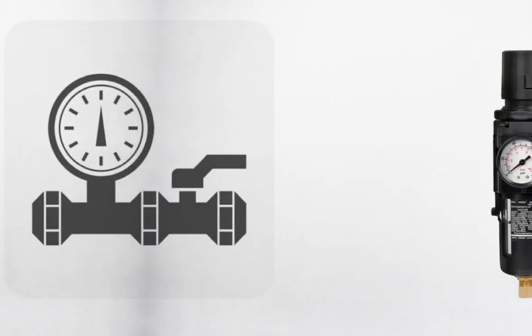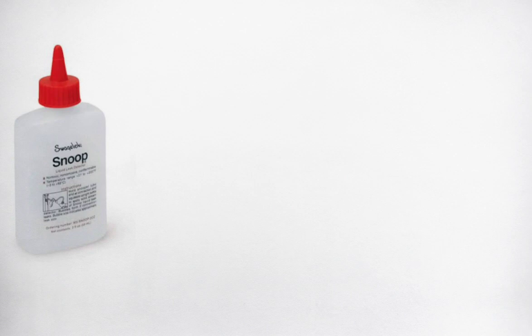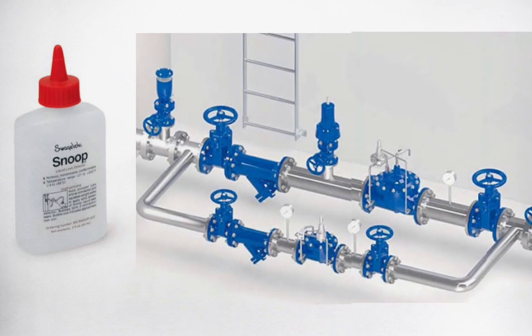Check the air pressure in the air filter and confirm its value with the air pressure mentioned in the control valve data sheet. Using a Snoop Liquid Leak Detector or any other leak detector, check all the air tubing and connections for air leakage.